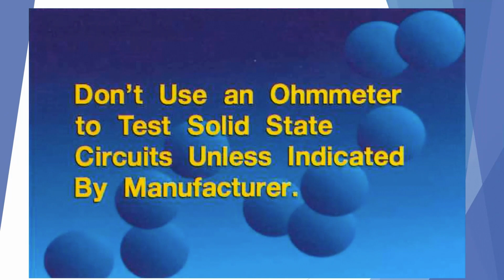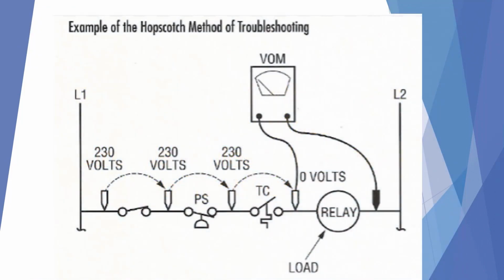This is because the ohm meter uses a battery to put a voltage out through the circuit to test it, and some solid-state devices cannot take those electrical charges. So check with your manufacturer and your troubleshooting guide before you make ohm readings on solid-state circuit boards. When an electrical circuit is not working, one of the most common methods of troubleshooting that circuit would be the hopscotch method. This is taking your voltmeter and starting at the source and hopscotch or jumping across each device to find out where you're losing the voltage to the relay or the motor or whatever device you're trying to energize.